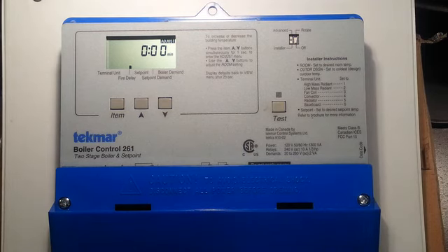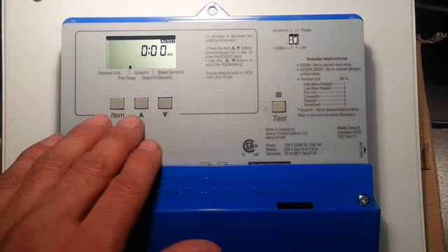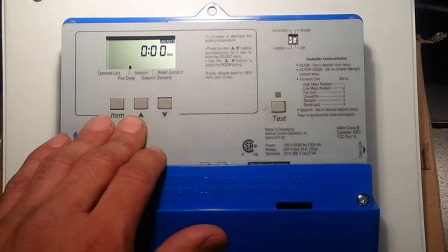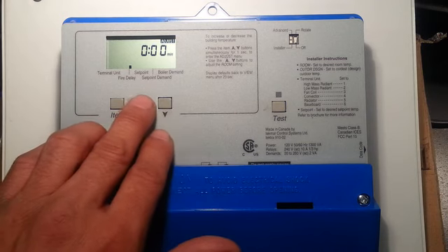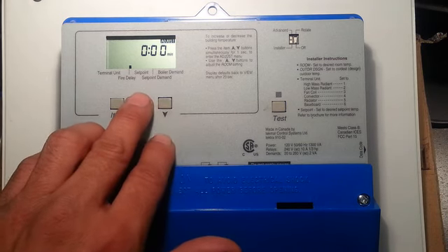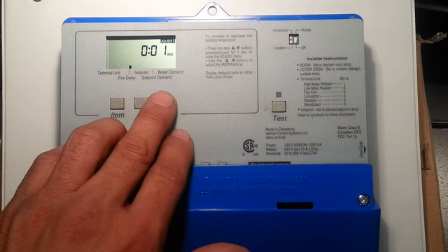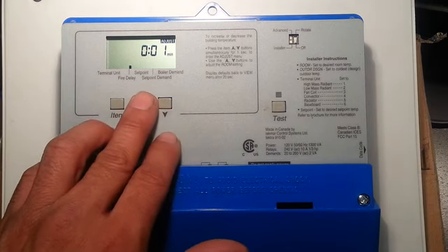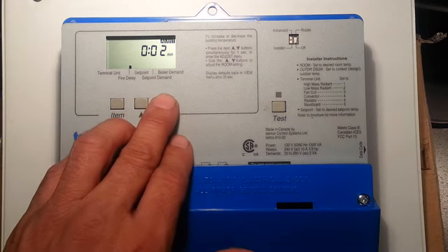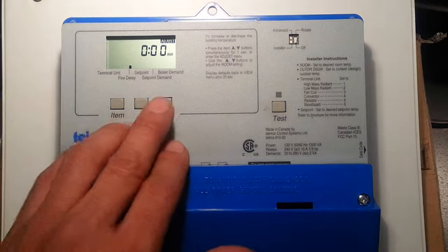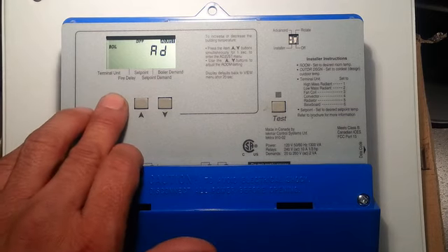The fire delay is typically found on more advanced boilers, something that has either an induced draft or a forced draft fan that causes the heat exchanger to need a timed purge. So if you have a purge that's a minute, you'd set this at a minute, or a 2-minute purge, you'd set this at 2 minutes correspondingly. But if it's an atmospheric boiler with no purge, just set it at 0, leave it like that.